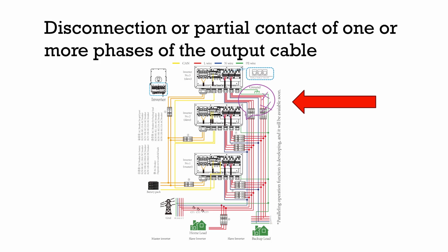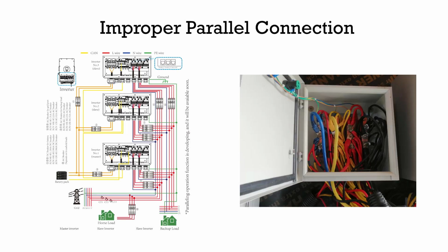So I've mentioned two things now that could lead to a parallel system shutdown on the side of your inverter system. First of all, if you don't do a proper connection to establish the parallel connection between your multiple inverters, by running each of the cables from, let's say, phase 1, phase 2, phase 3, and the neutral to a bus bar, connecting each of those ones to the bus bar, then taking just one thicker cable from each of those lines on the bus bar to supply your load. If that is not properly done, you can actually have a parallel system stop, which is the F41 error.